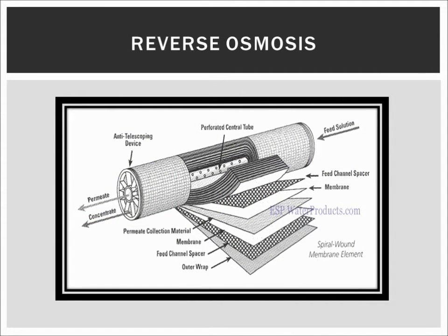The RO process is the keystone portion of the seawater treatment process. This process filters out all suspended solids and the majority of dissolved solids. RO is implemented through the use of membrane technology filters, which remove molecules and ions from the solute. This is achieved by applying a force to a solvent in excess of the osmotic pressure.